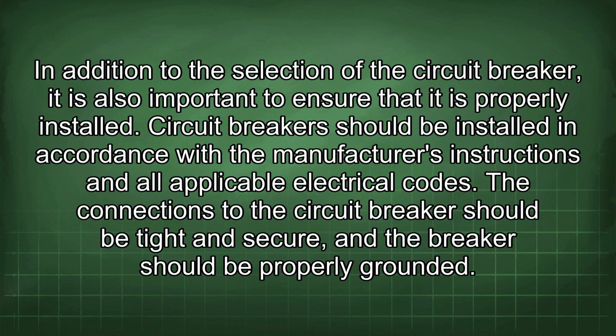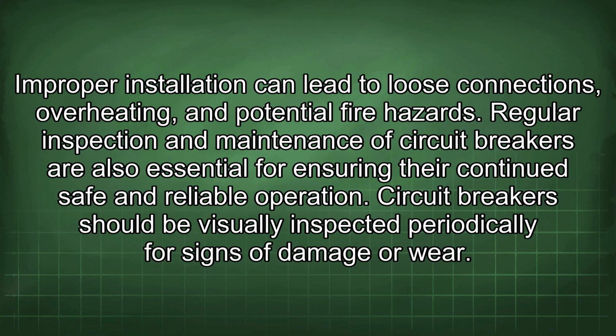In addition to the selection of the circuit breaker, it is also important to ensure that it is properly installed. Circuit breakers should be installed in accordance with the manufacturer's instructions and all applicable electrical codes. The connections to the circuit breaker should be tight and secure, and the breaker should be properly grounded. An improper installation can lead to loose connections, overheating, and potential fire hazards.